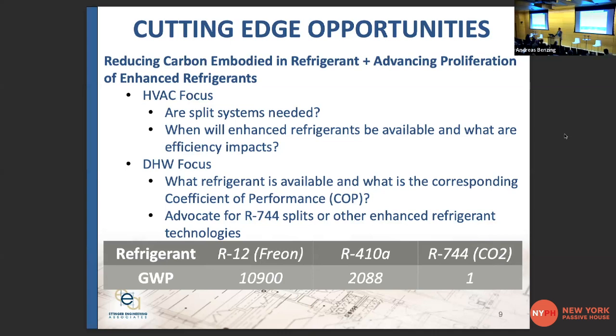In the domestic hot water space, the hot water coming out of our showers and sinks, we're making a lot more progress. A lot of the equipment available has already come to terms with enhanced refrigerant. There are R744 domestic hot water systems at a large scale, central, and even mini splits. The real question is what refrigerant is in this equipment and what it does to the coefficient of performance, the efficiency rating for the domestic hot water equipment.